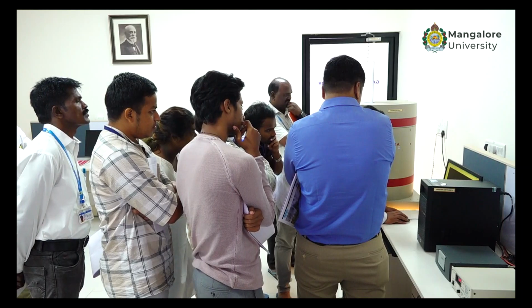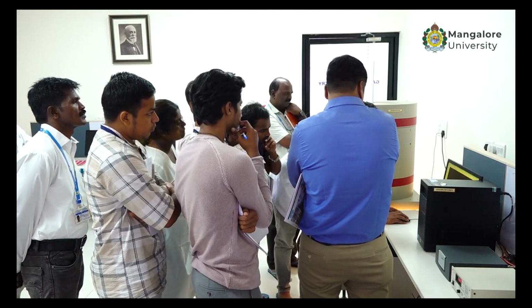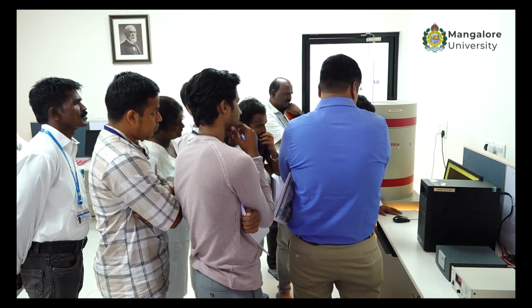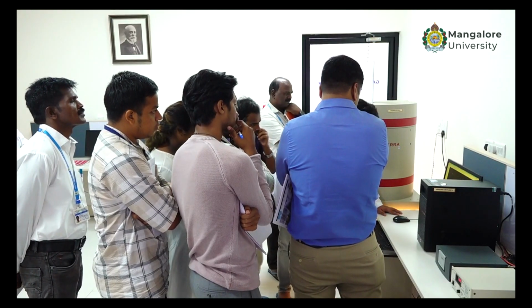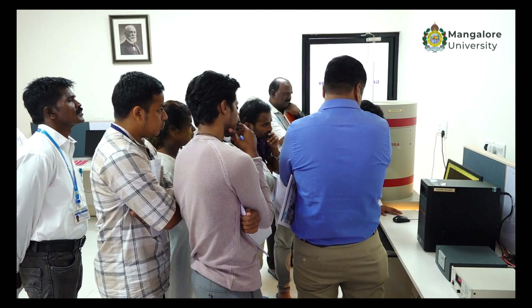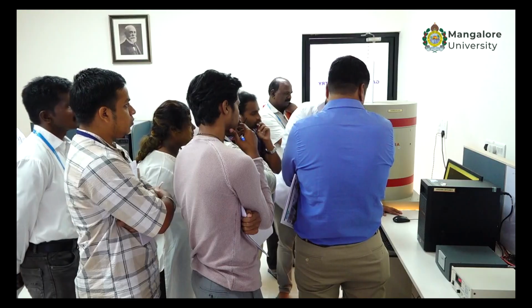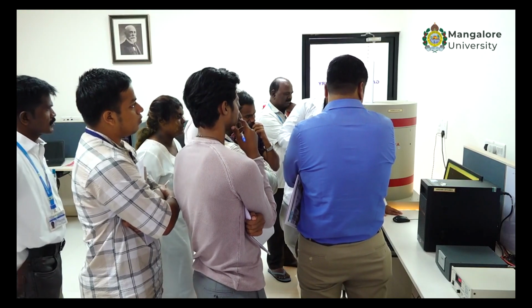Yeah, 45.6. It has counts of 2368. This one channel. The next channel over here has counts of 2463. So on, so on. You have 9,000, 10,000, again 9,000. 46.8 has a peak energy of 10,250.